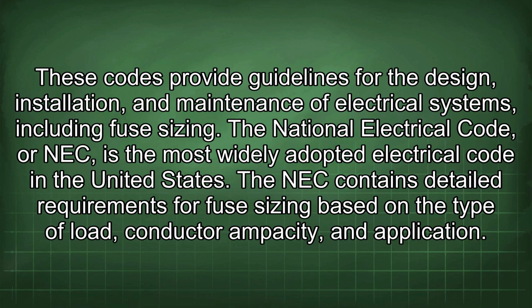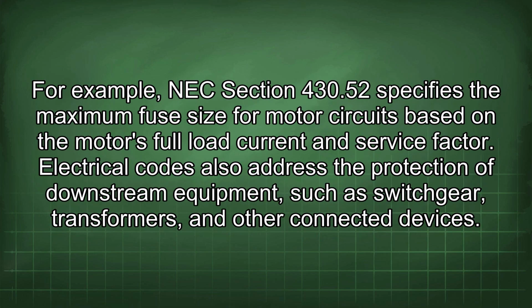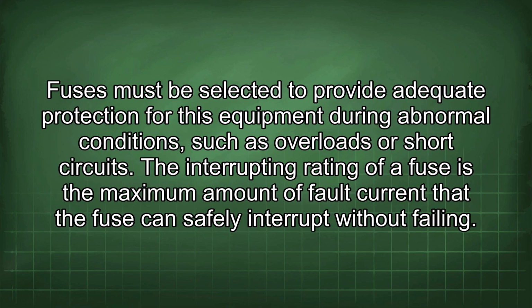The NEC contains detailed requirements for fuse sizing based on the type of load, conductor ampacity, and application. For example, NEC Section 430.52 specifies the maximum fuse size for motor circuits based on the motor's full load current and service factor. Electrical codes also address the protection of downstream equipment, such as switchgear, transformers, and other connected devices. Fuses must be selected to provide adequate protection for this equipment during abnormal conditions such as overloads or short circuits.